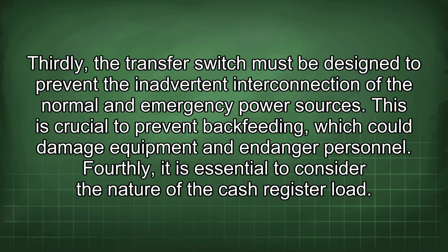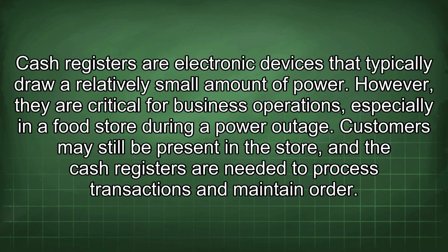Thirdly, the transfer switch must be designed to prevent the inadvertent interconnection of the normal and emergency power sources. This is crucial to prevent backfeeding, which could damage equipment and endanger personnel. Fourthly, it is essential to consider the nature of the cash register load. Cash registers are electronic devices that typically draw a relatively small amount of power. However, they are critical for business operations, especially in a food store during a power outage. Customers may still be present in the store, and the cash registers are needed to process transactions and maintain order.